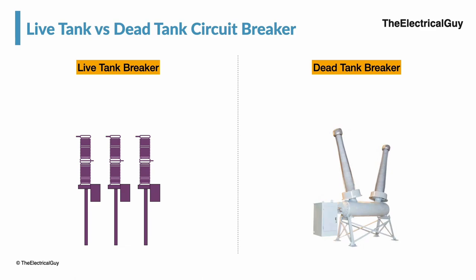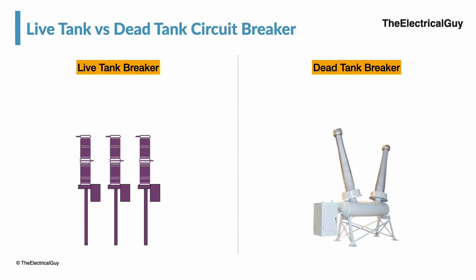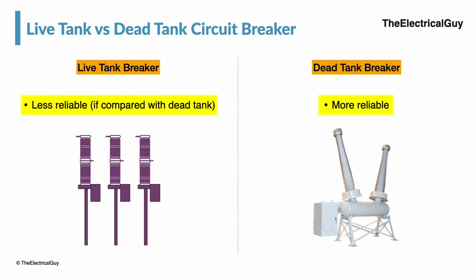Dead tank circuit breakers come completely assembled from the factory and do not need any major assemblies at site, whereas a live tank circuit breaker does not come fully assembled — major assemblies are required at site. Since the interrupter unit is completely secured in the metal-encapsulated tank and seismic performance is better, dead tank circuit breakers are more reliable than live tank breakers.